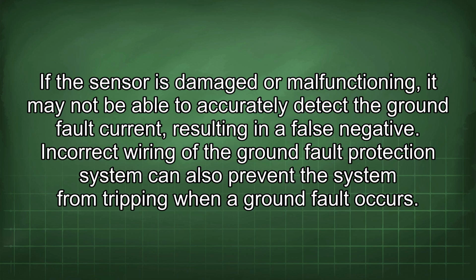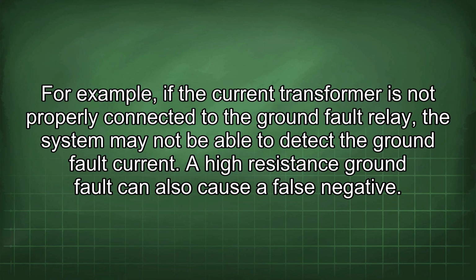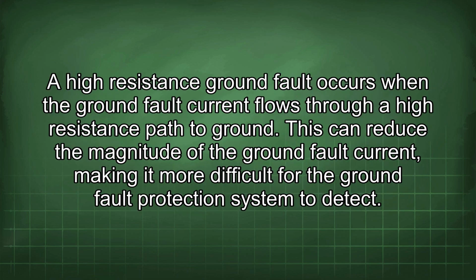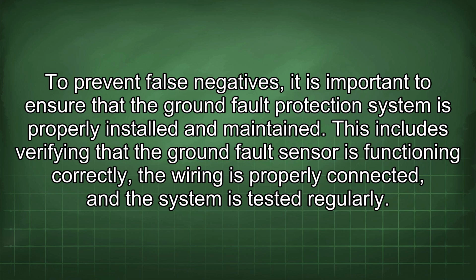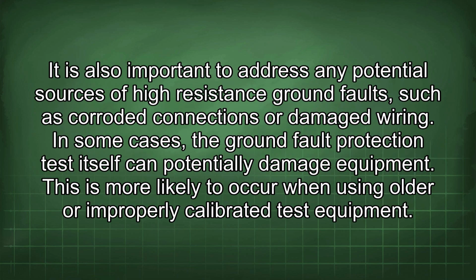Incorrect wiring of the ground fault protection system can also prevent the system from tripping when a ground fault occurs. For example, if the current transformer is not properly connected to the ground fault relay, the system may not be able to detect the ground fault current. A high resistance ground fault can also cause a false negative. A high resistance ground fault occurs when the ground fault current flows through a high resistance path to ground. This can reduce the magnitude of the ground fault current, making it more difficult for the ground fault protection system to detect. To prevent false negatives, it is important to ensure that the ground fault protection system is properly installed and maintained. This includes verifying that the ground fault sensor is functioning correctly, the wiring is properly connected, and the system is tested regularly. It is also important to address any potential sources of high resistance ground faults, such as corroded connections or damaged wiring.